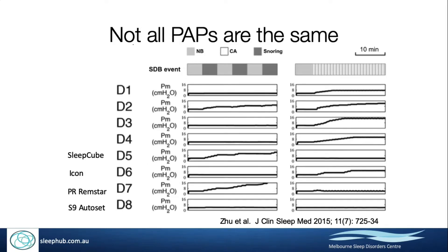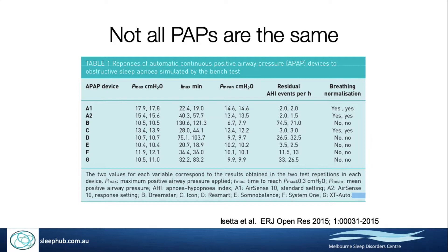From the same paper, this looks at the machine's ability to respond to snoring in the middle panel and to central apneas in the right-hand panel — again, a range of different results. The interesting finding is in the right-hand panel: what you want from a PAP device is for it to not increase pressure in response to central apneas. Yet the majority of devices actually did increase pressure in response to simulated central apneas, rather than recognizing them as central apneas and maintaining the same pressure.